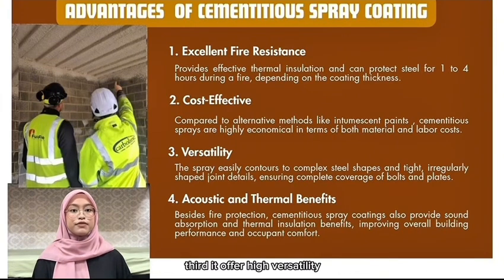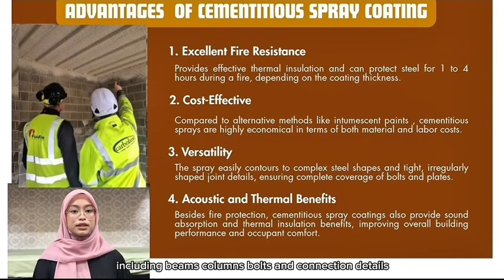Third, it offers high versatility. The spray can easily cover complex steel shapes, including beams, columns, bolts, and connection details, ensuring complete fire protection even in irregular areas. Lastly, it provides acoustic and thermal benefits.